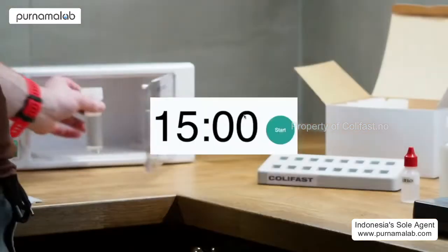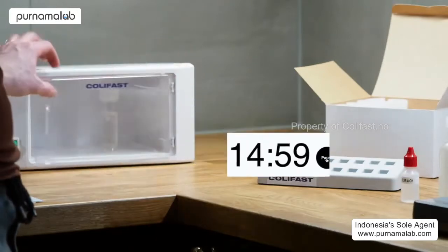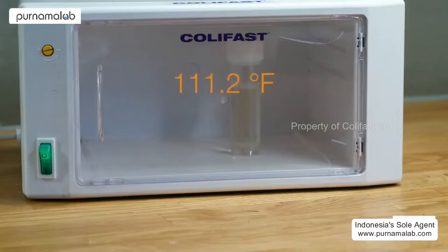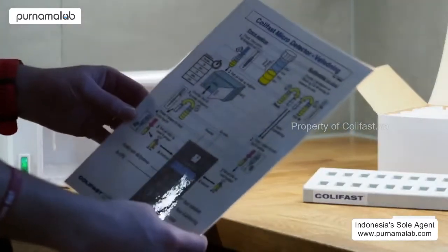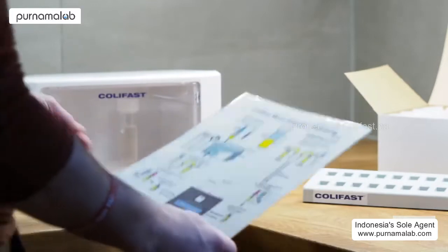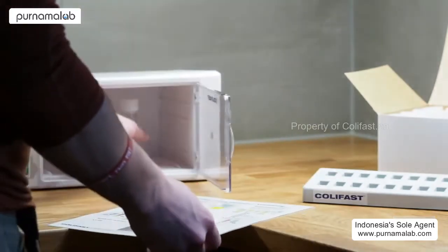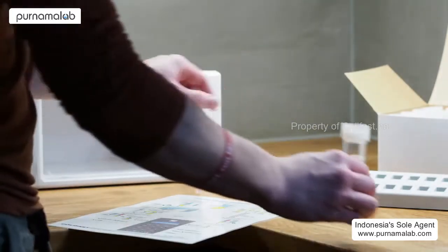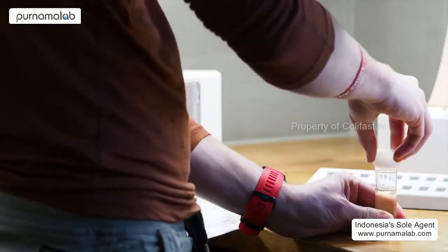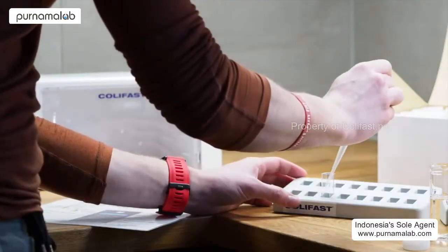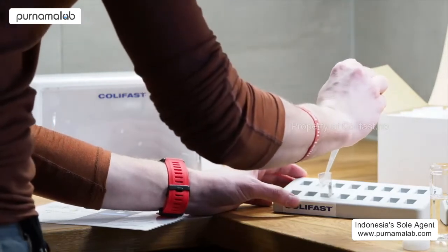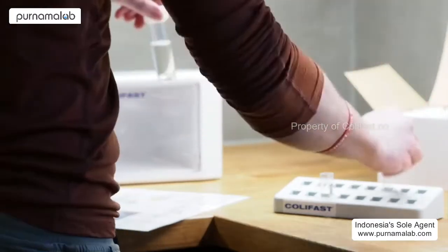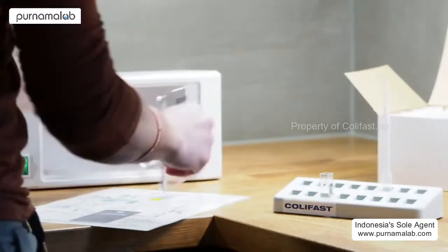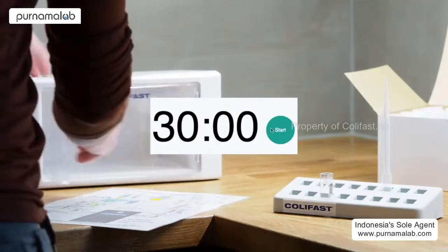Incubate the prepared sample for 15 minutes at 44 degrees Celsius. The temperature is selecting for thermotolerant bacteria, and the medium is selective of coliforms, yielding the specificity of the test. Now, after 15 minutes, take out the sample and prepare the first measurement. 3 milliliters are pipetted from the vial using a pastette, and the sample is poured into the cuvette. The sample goes back into the incubator for another 30 minutes.